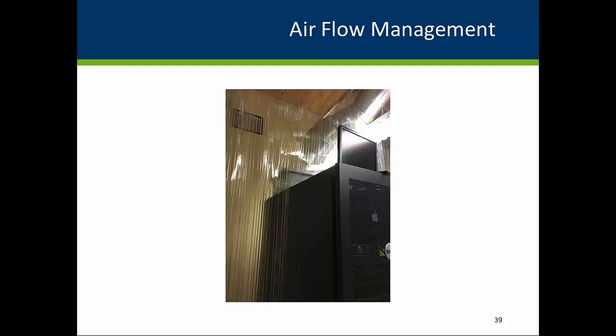From our temperature monitoring, we found that in SEDCs with dedicated cooling, there was a lot of mixing between the cold air supplied to the rooms and the heated air exiting from the server racks. This resulted in high uneven temperatures measured at the front of the server racks. Cold and hot aisle containment can not only reduce cooling loads, but also ensure better control of server inlet temperature.